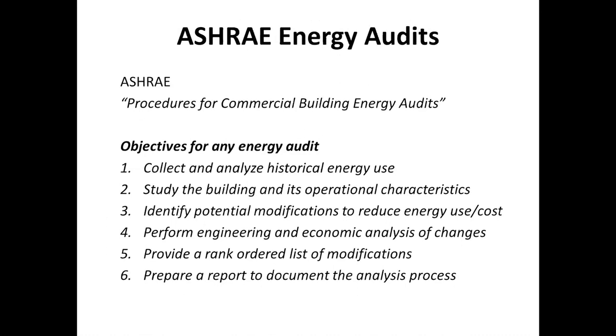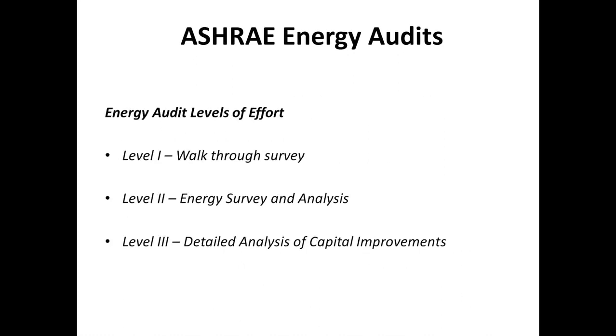audit. So to delve a little bit further into ASHRAE energy audits, the main theory is that you're going to collect and analyze historical energy use. The best practice would be to obtain at least 24 months of utility bill data and analyze the most relevant and most recent data, using the second year of backup data to adjust any anomalies and to ensure that there were no outliers in the data. Also look at the building and operational characteristics. Look for outliers in the operations of the building, perform energy and economic analysis for changes, and provide a list of ranked modifications in the form of energy conservation measures.